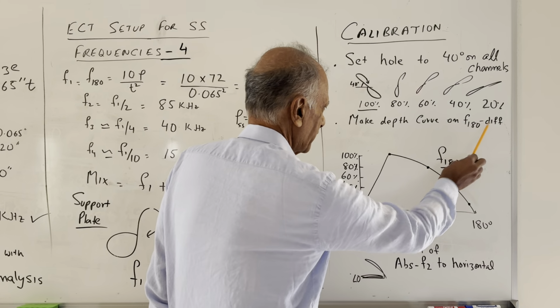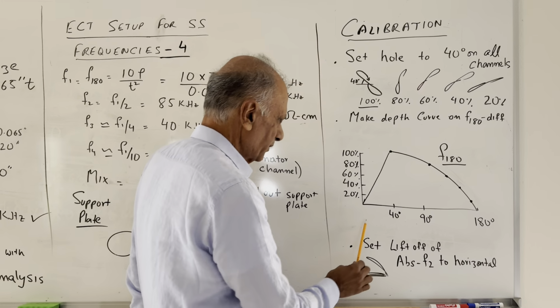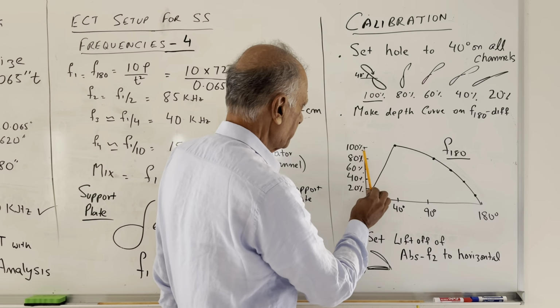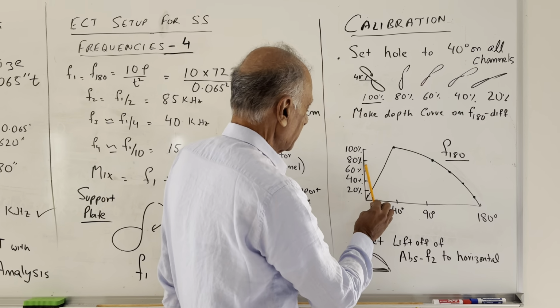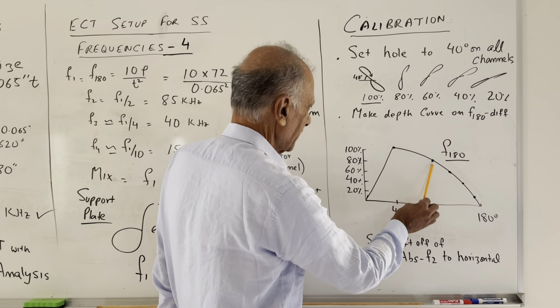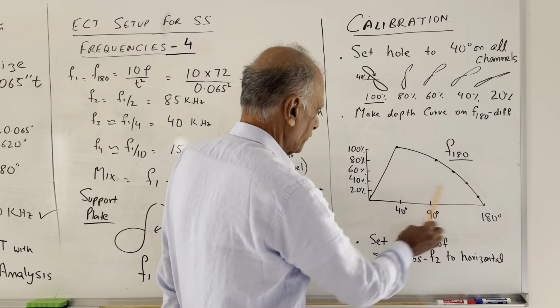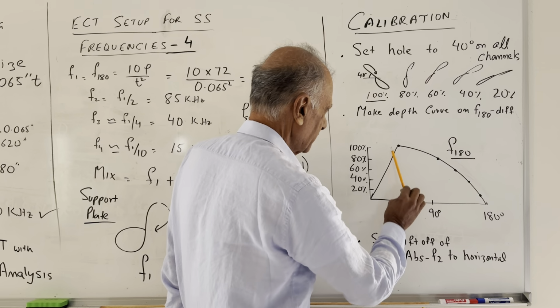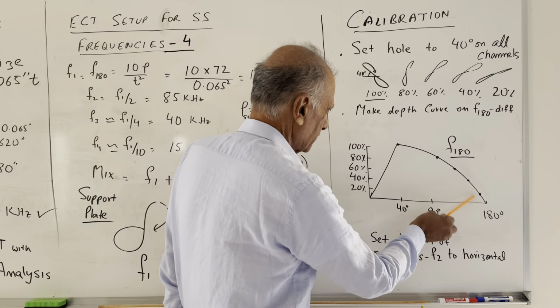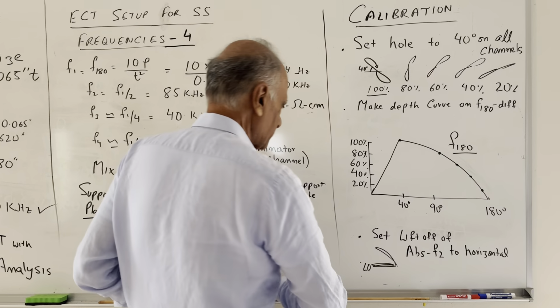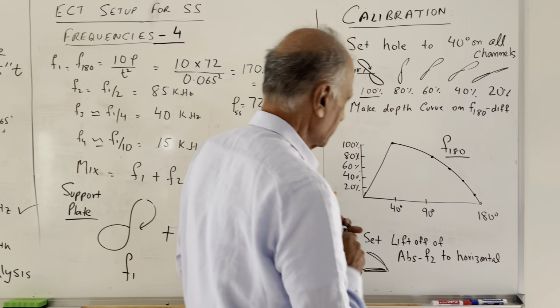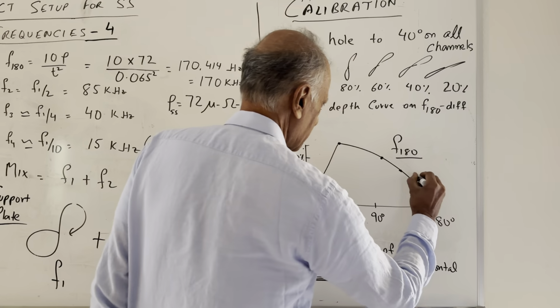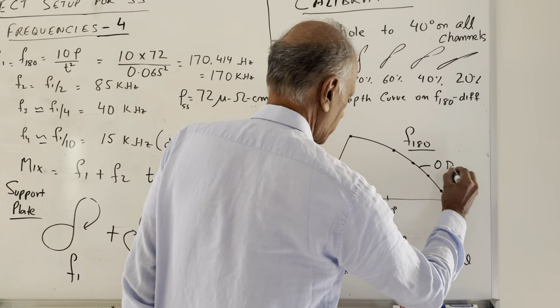and the ECT instrument will actually make a depth curve on the F1 differential channel, and it's going to be looking like this. At 100% is 40 degrees, then 80%, whatever is the angle, then 60 and 40 and 20. And you can see that it creates a phase spread. It creates from 40 degrees to 180 degrees. So this is really the OD flaws.